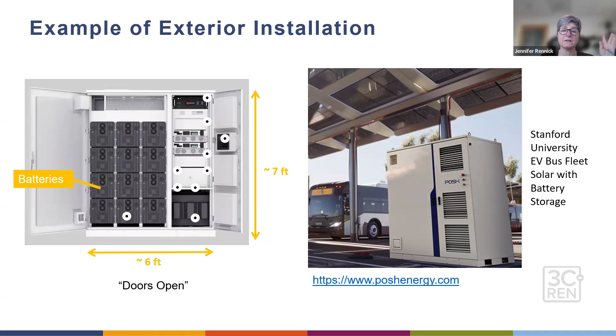Energy storage system permitting, BESS or ESS depending on which section of the code you're reading, lays out the requirements you have to have on your construction documents. This is an excerpt from Chapter 12, Title 24, Part 9. For the 2025 code, it more explicitly lists the requirements, saying a fire plan is also required. It talks about fire suppression, thermal management, ventilation, exhaust, etc., and a decommissioning plan, which is key because what happens at the end of the life of the battery - that decommissioning is supposed to be part of your whole permitting process.